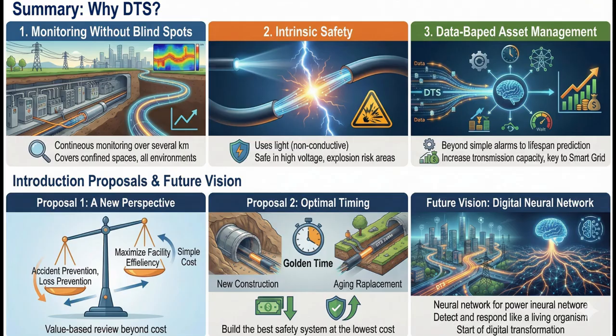A customer decision guide can be summarized in 3 sentences. First, DTS eliminates blind spots. Second, it is inherently stable because it is fiber-optic based and remains strong even in EMI environments. Third, it accumulates data and expands into asset management and operational optimization. DTS is ideal for new installations, but a phased rollout starting with aging sections or high-risk joints can also be highly effective. Over the long term, DTS becomes foundational data for a digital power grid.